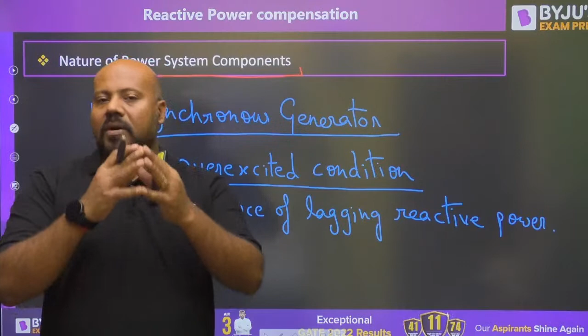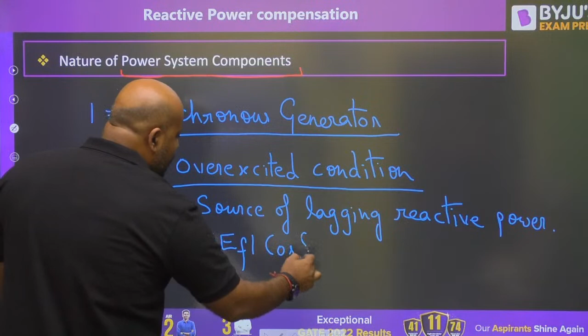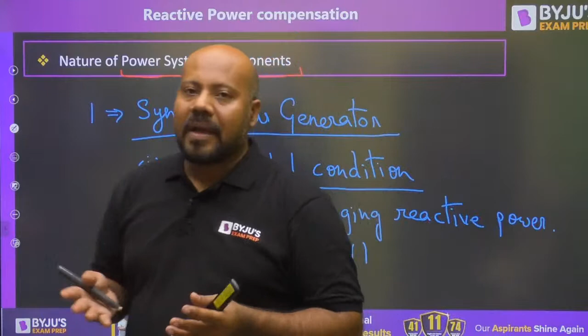So the first thing we are saying about the overexcited condition is that your generator is going to act as a source of lagging reactive power. The second thing is, for the overexcited condition, mod EF cos del is going to be more than mod V, where EF is the excitation EMF, del is the load angle or torque angle, and V is the magnitude of the terminal voltage. This is the condition for the overexcited condition.